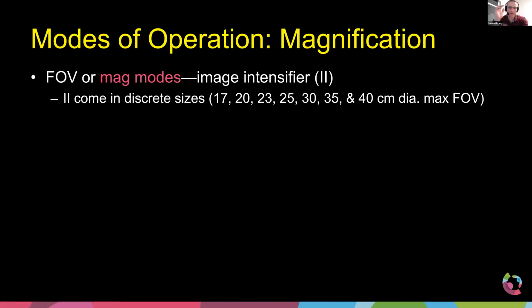We talked a lot about controlling the noise, so collimating, using grids, or, if in some future day we have it, some fancy reconstruction technique. The next step down along the list of image quality optimization is how we operate the system. Remember, no kV knob, no mA knob, so it's all about how we actually use the system to then affect how our eyes see the image. So one of the most simple ways to improve contrast or resolution is magnification. We've been doing this in fluoroscopy for a very long time.